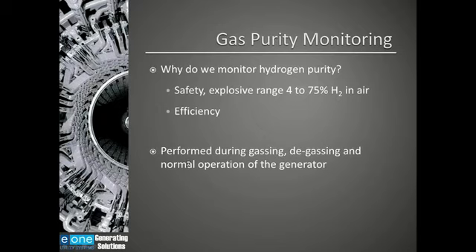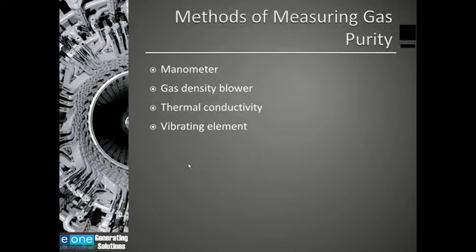The most frequently used technologies are thermal conductivity analyzers. There are different types of thermal conductivity analyzers. The one thing they have in common is that they all use a thermistor as a sensing device. However, the type of thermistor and the electronics that are used can vary greatly from analyzer to analyzer. There is a vibrating element analyzer. This is a newer technology. It is important that your analyzer is a triple range analyzer that can determine not only hydrogen and air during normal operation, but also hydrogen and CO2 and air and CO2 during the gassing and degassing process of the generator. It is also very important that these devices, since they are analyzing hydrogen, be rated to be used in a hazardous area.